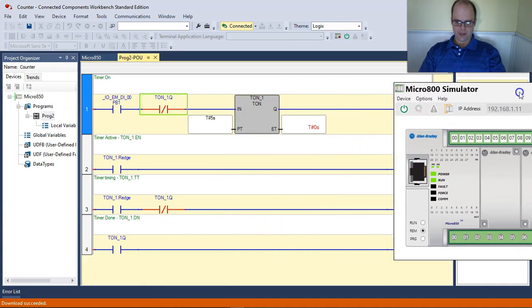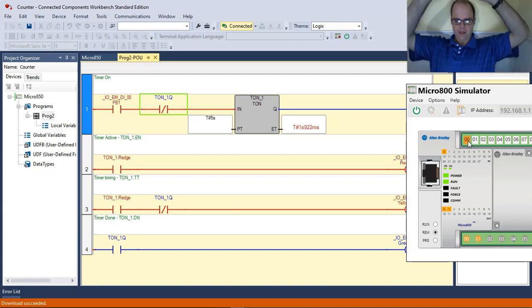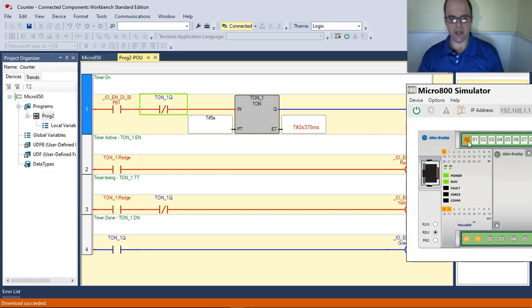I'm just going to have this over here because I think you can still see everything, and you can see these three lights. And I'm going to hit this push button, and I'm going to let go. And watch what happens to that elapsed time. Is it ever getting to 5 seconds? No, because once the millisecond that this becomes true, it actually resets itself.